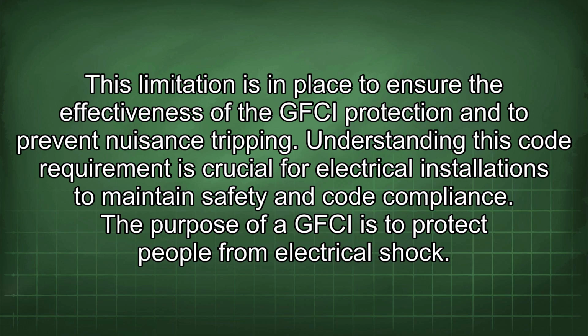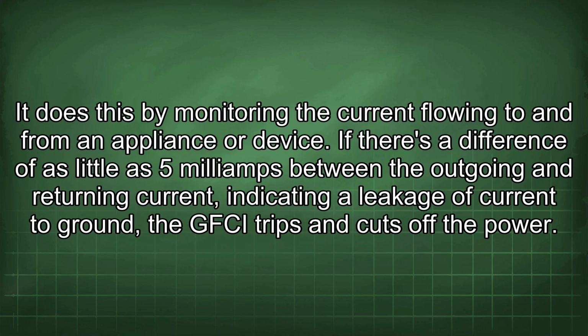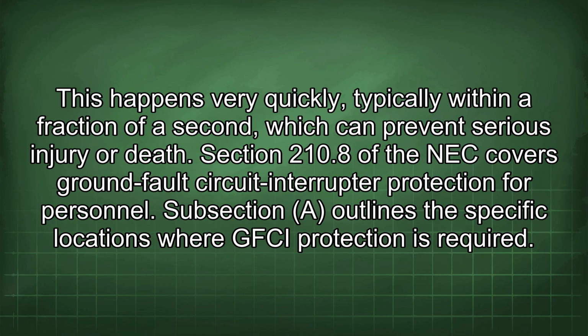The purpose of a GFCI is to protect people from electrical shock. It does this by monitoring the current flowing to and from an appliance or device. If there's a difference of as little as 5 mA between the outgoing and returning current, indicating a leakage of current to ground, the GFCI trips and cuts off the power. This happens very quickly, typically within a fraction of a second, which can prevent serious injury or death.